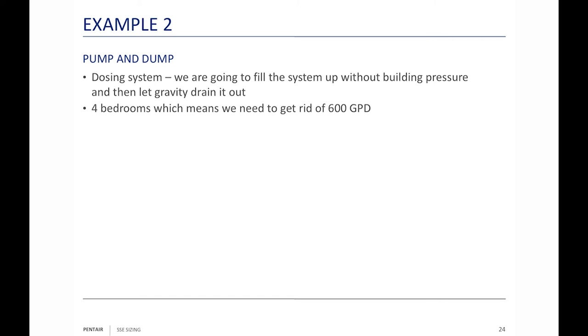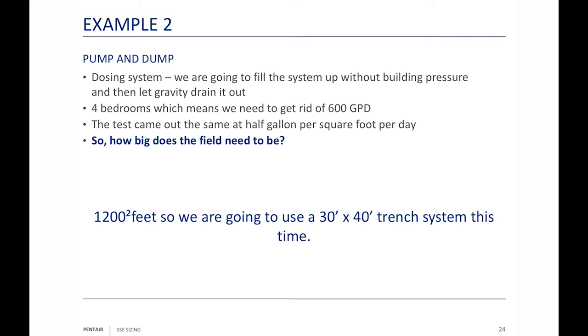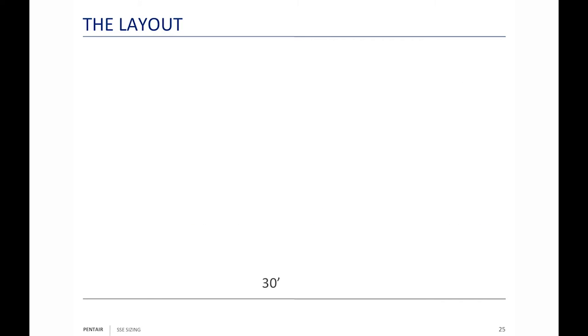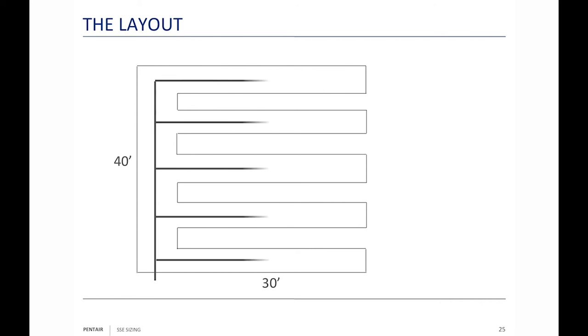Since it's a dosing system, the pump only turns on when there's enough water present. Our percolation test is again 0.5 gallon per square foot per day, so the field needs to be 1,200 square feet. We'll use a 30-by-40 trenching system this time, unlike the bed used in Example 1. We dig 40-foot-long trenches and put in 4-inch pipe as laterals, running 30 feet in the perpendicular direction. The larger pipe lets us fill the system and then let gravity slowly distribute it — we don't want to force it.